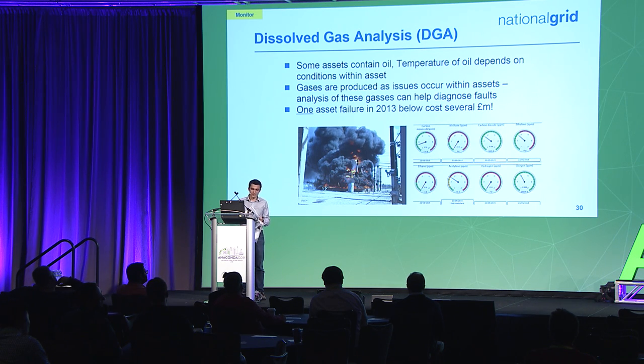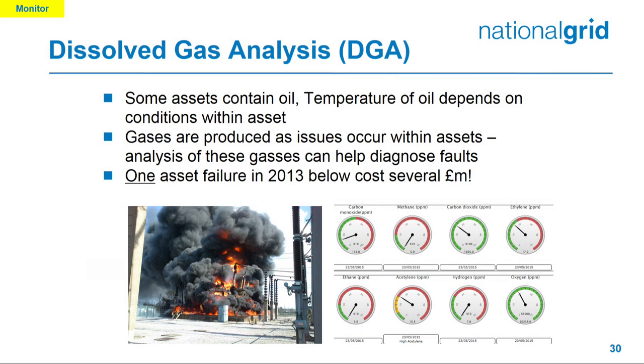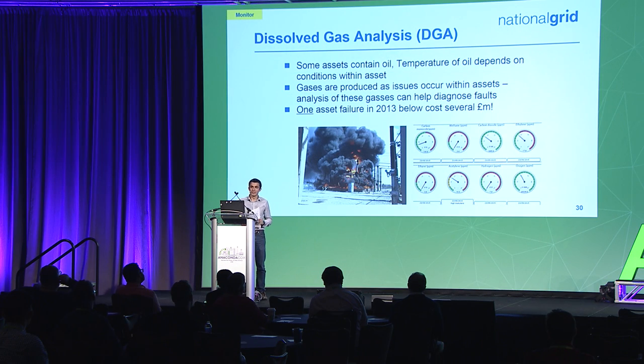This is an example of when things go wrong — a transformer fire that happened in 2013. The oil is actually well contained at the bottom; there's a concrete bund at the bottom containing all the oil. So it's obviously in our interest to maintain transformers and analyse the oil inside them, because there's no other way of really telling the condition of a transformer without sampling the oil. The oil samples get sent off to a lab, they send back the results, and we can start trending that.